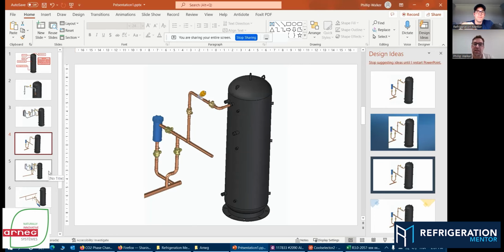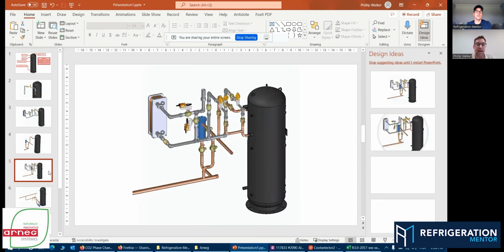A lot of the machines as well will look for a 10 to 15 pound pressure drop across the filter or across the oil separator. So we know indeed it's time. I can't count the endless stories where we're just on autopilot. We change filters for no reason other than changing filters, right? Yeah, you don't have to do that. So I just meant, and that's a great explanation, pleated filters or solid core filters? Oh, solid core filters. Solid core. Yeah, okay, thank you. Yeah, that's what we're currently using right now. But most market filters are absolutely fine, at least for our systems.